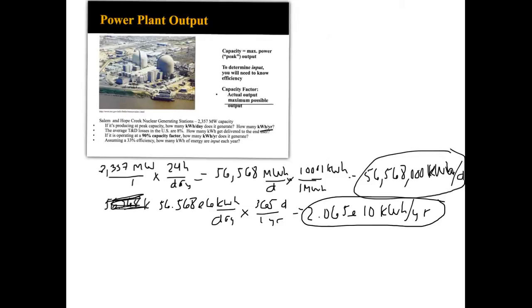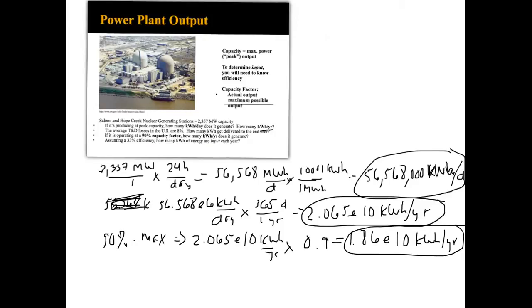So let's actually skip to the third one here. If it's operating at a 90% capacity factor, how many kilowatt hours a year does it generate? So our capacity factor is our actual output divided by our maximum possible output. So really, it's 90% of this. So 90% of the maximum. So it's 2.065 times 10 to the 10th kilowatt hours per year times 0.9, which is going to give us exactly 1.86 times 10 to the 10th kilowatt hours per year. So that is a more realistic number. I mean, 90% is a pretty reasonable capacity factor for a coal-fired power plant because it's baseload. It's operating at pretty full capacity most of the year.